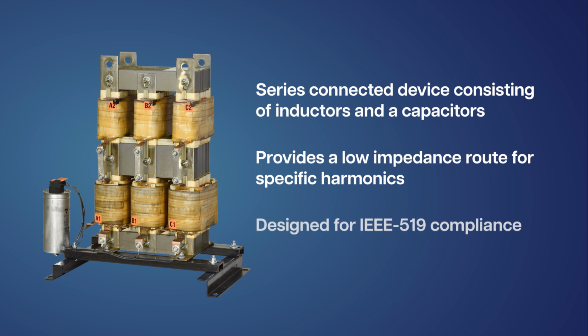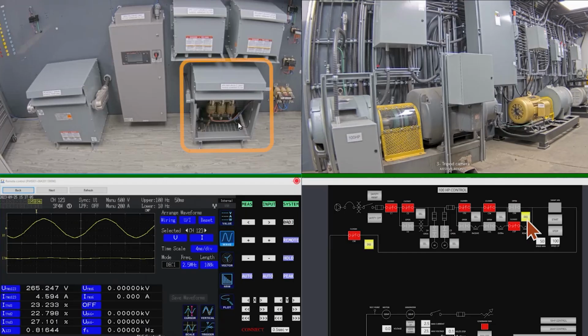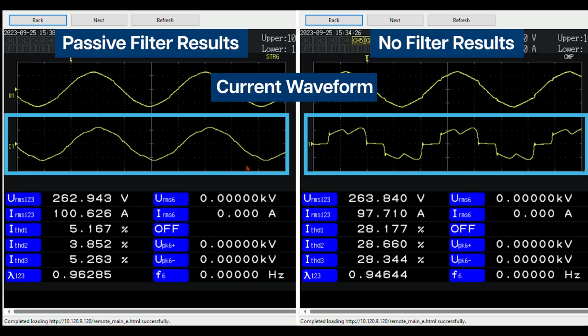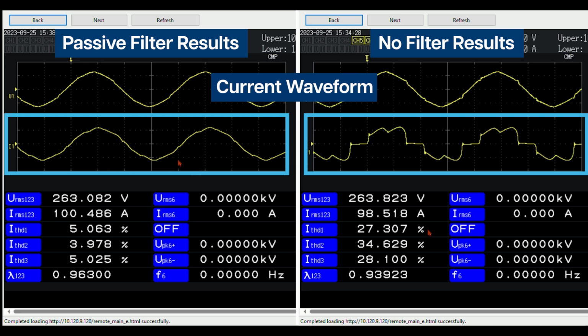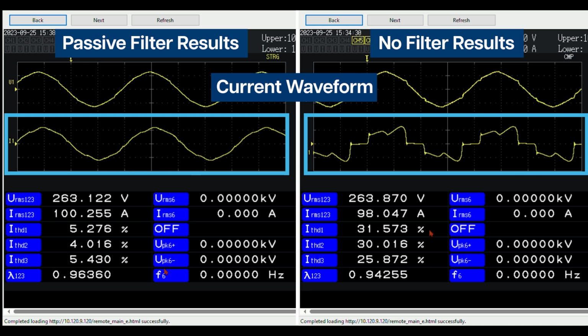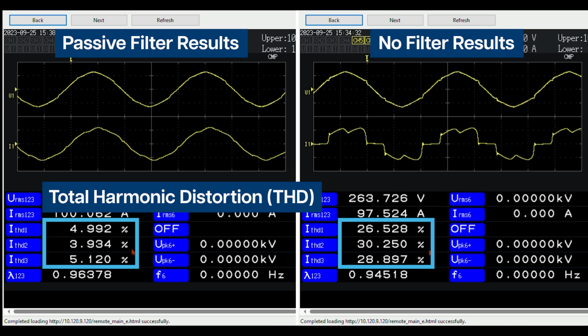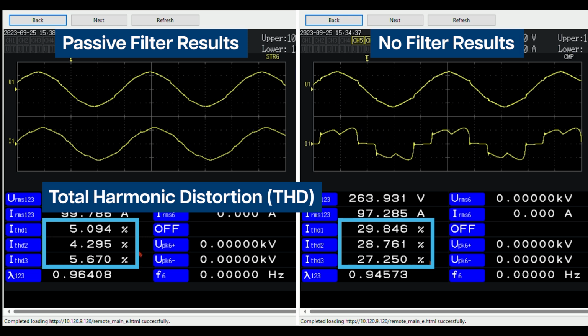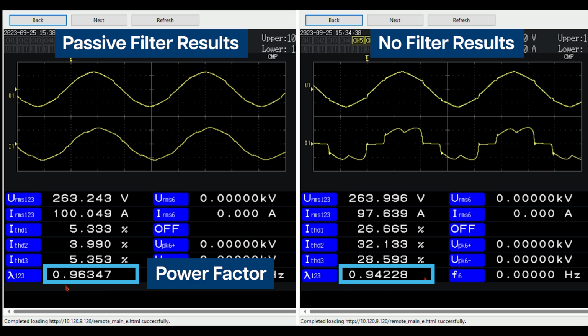It is designed with IEEE 519 compliance in mind, and passive harmonic filters are particularly well suited for configuration with a smaller number of VFDs or for loads exhibiting a stable harmonic profile. The average total harmonic distortion is reduced to less than 5%, and power factor is improved.